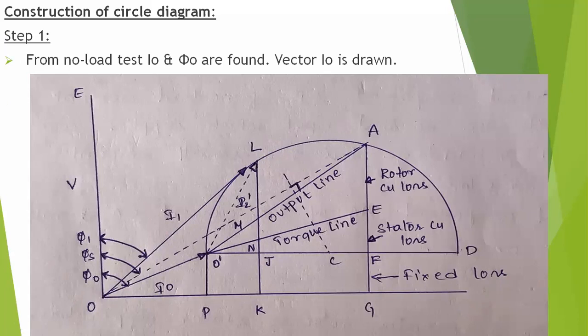For drawing the circle diagram, we have to collect the following data. First, the stator resistance test — we have to conduct this test for separating stator and rotor copper loss. Second, the two tests of induction motor: no load test and blocked rotor test. Blocked rotor test is also called the short circuit test.